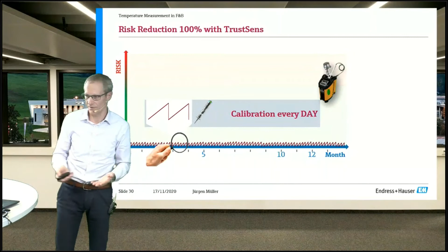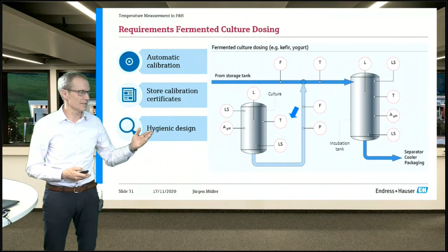Therefore, I picked another application. In this case, it is the fermented culture dosing in the dairy industry when you produce yogurt, for example. And I looked at the temperature measurement in the culture tank and asked myself, what would be nice to have as a technical feature for the thermometer that you use in this case? And it is, as you see indicated here, the automatic calibration, which is triggered automatically, of course. And whenever you do a calibration, the calibration protocols should be stored and also transferred to a data management system if you need that. And of course, we need the thermometer in hygienic quality.